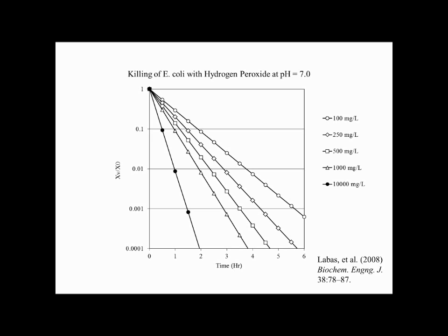So we'll come back to talk about it later, but there's two concerns about what I'm talking about in time. One is the time that we actually spray the solution or have it soaking, and the other is how long the surface is wet. So if we wash a tank and we spend 10 minutes washing it, the real question is how long does it take to dry? Because the killing chemistry is still working while we're drying. And so if you washed a tank out, probably an hour later it might have dried out, depending on the humidity in the room you're in. But in many cases it's still wet an hour later. And as a result, it would still be killing, even if we took the solution away.